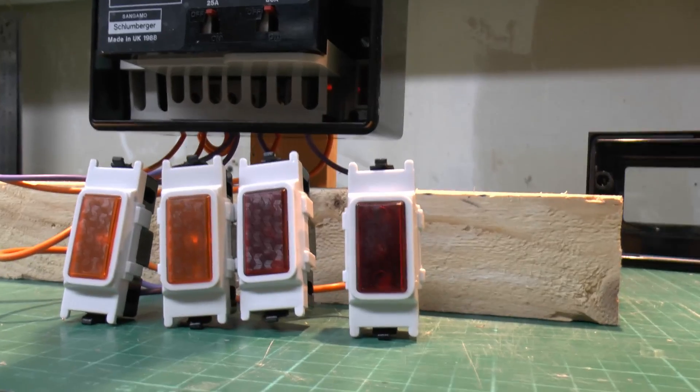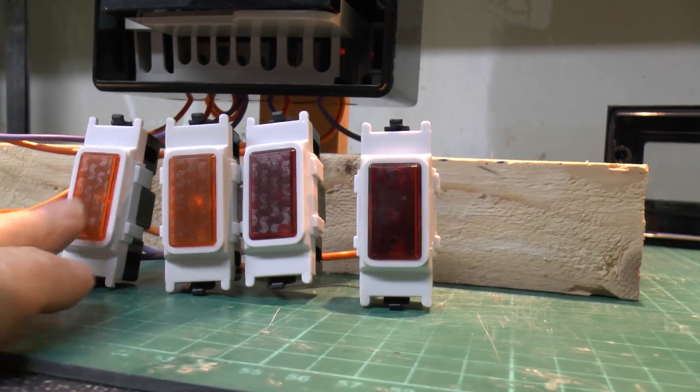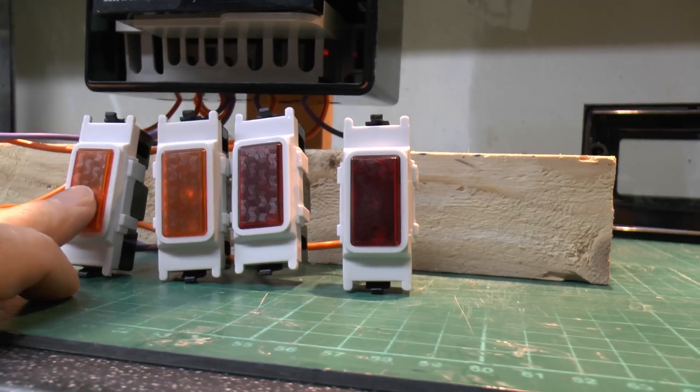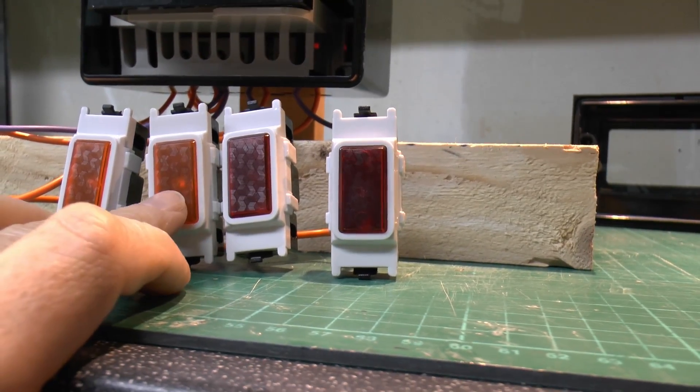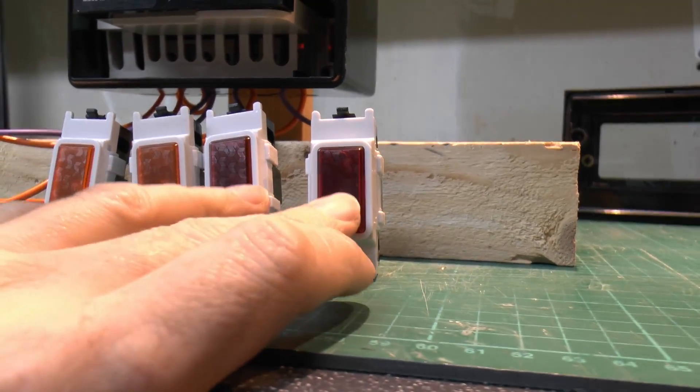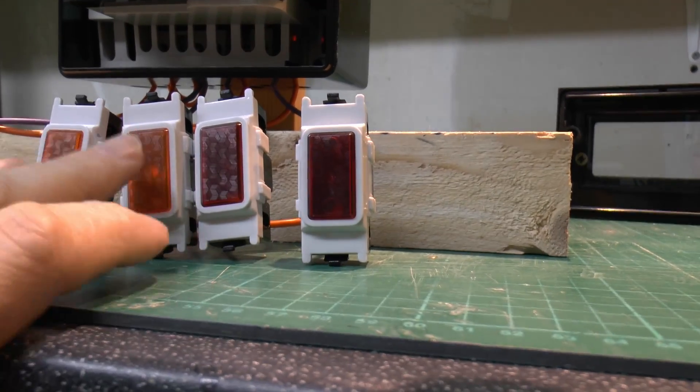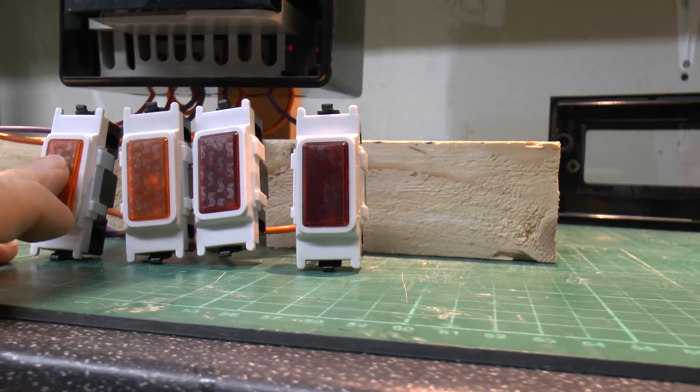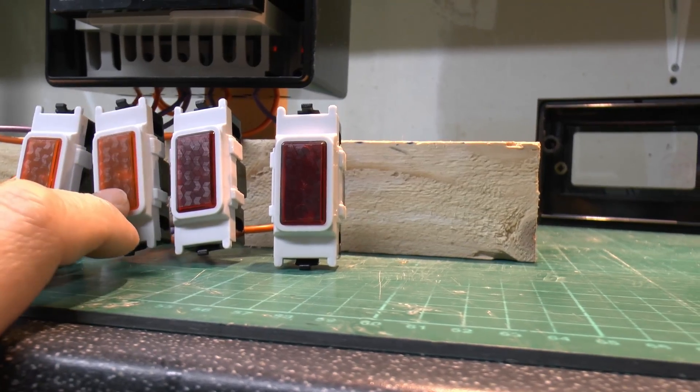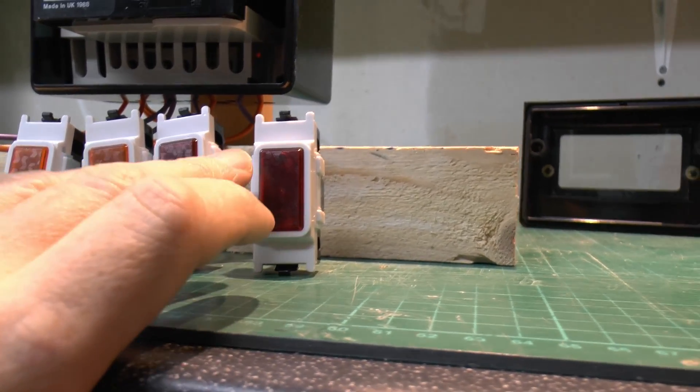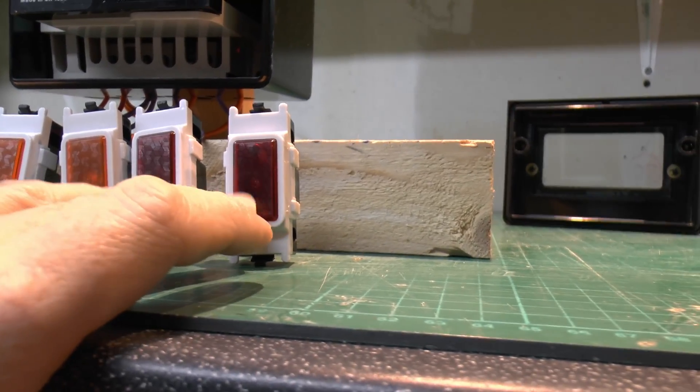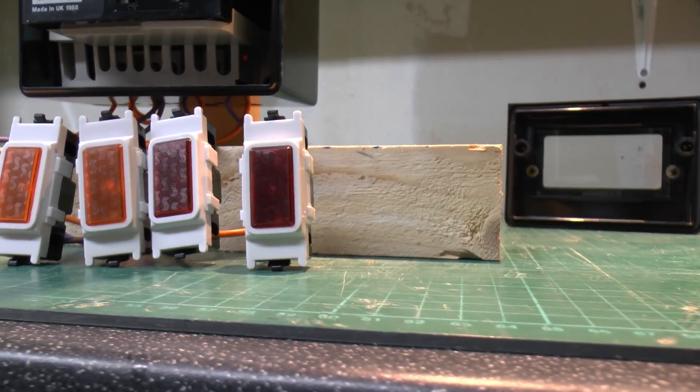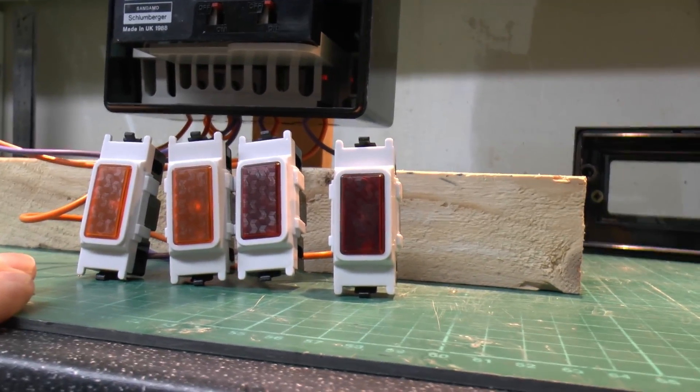Now I've actually wired up at the bottom these neon indicators here. So we've got four of these. This one is for the 25 amp output, this is for the 80 amp output, and then we've got two here which are the switched neutral outputs, which should switch at the same time as these two. So that would normally be for your hot water, the 80 amp one would be for the storage heaters, and then these two neutral switch ones would be for the electricity meter to select the various different rates, so you are obviously charged accordingly.